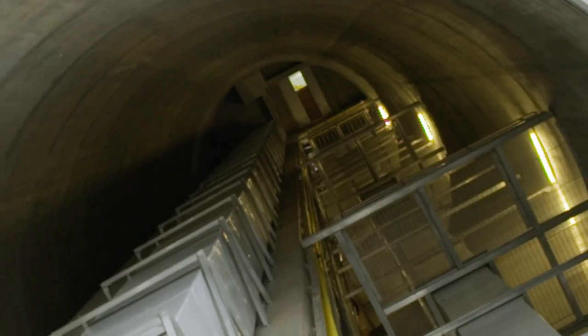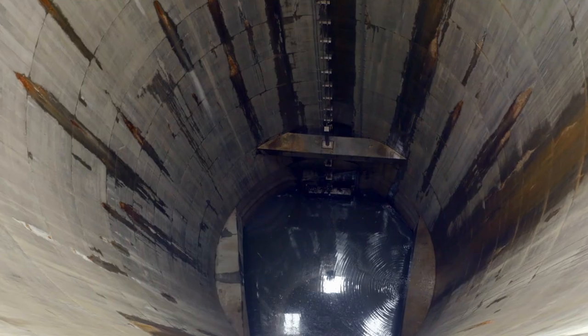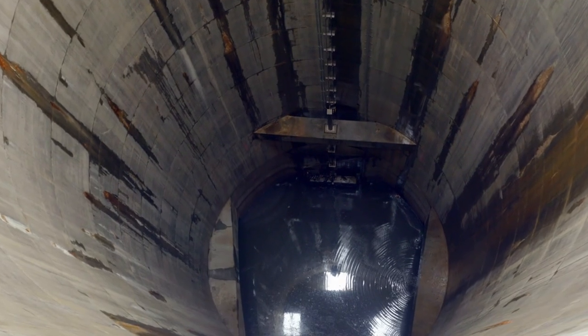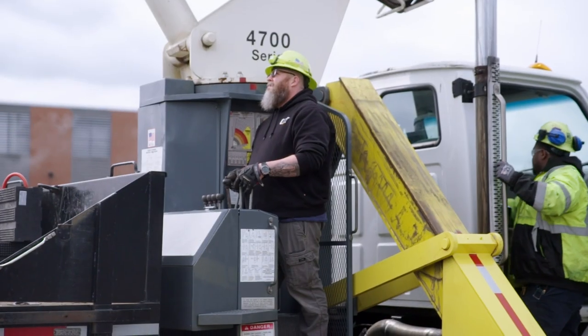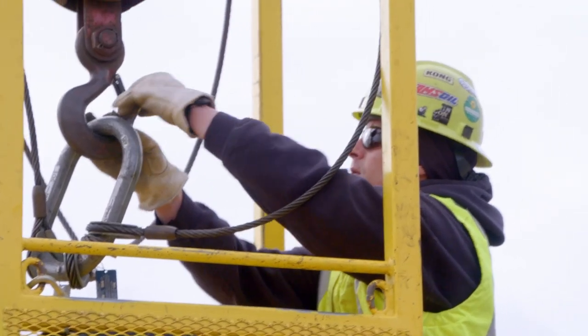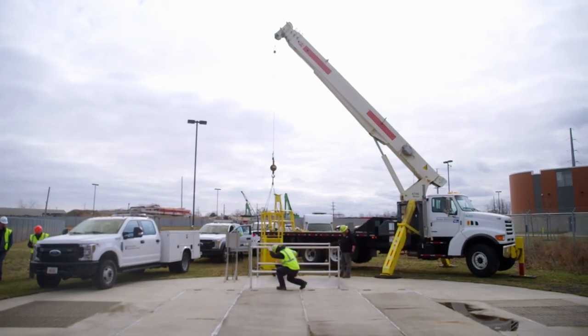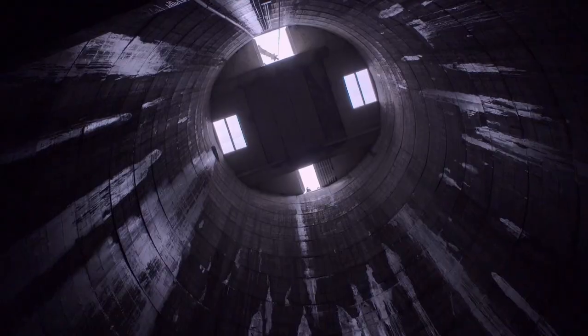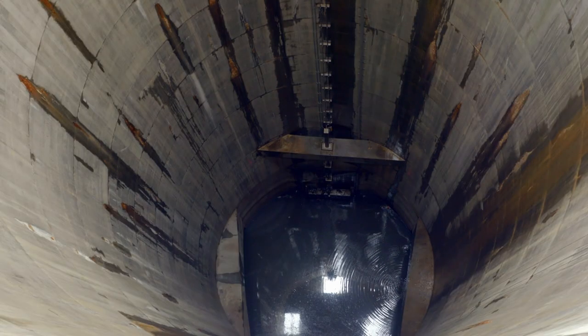This is a very important sector of the pump station, and they don't want it overflowing. The gate sits roughly 22 stories below the ground, requiring a crane for inspection. They inspect all the hardware, and once down there, inspect the gate to make sure there's no heavy debris, no logs wedged in, no metal pieces wedged in anywhere. Todd needs to be incredibly cautious — it's definitely dangerous, hanging from a wire rope. At 220 feet, one slip can be deadly.